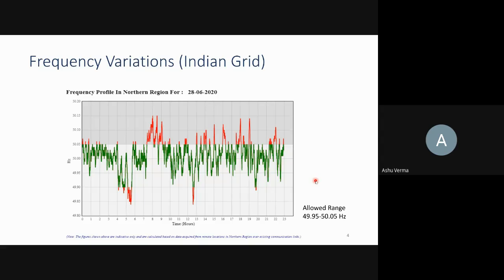Voltage is a more flexible constraint compared to frequency. Even at your household, voltage should remain near rated value, within a good range of plus minus 5%, or plus minus 10%. So any bus voltage should always remain between 0.9 to 1.1 per unit. At times voltages go even below or above that range, which impacts equipment and other things, but nothing much adverse happens. Frequency, however, is a comparatively stiffer band and a more stiff constraint that we have to satisfy at all times.